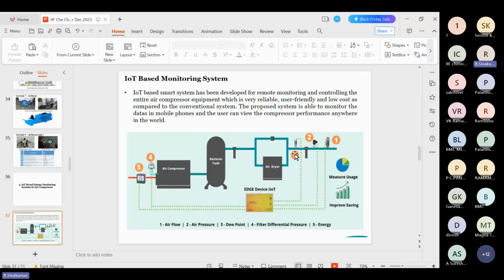There is one device for that. Fourth is the differential pressure, that is the inlet and outlet differential pressure. And finally, the fifth one is the energy meter. If the energy meter is not available, we put our power quality analyzer at the input of the air compressor, so that we monitor the pressure generation and the CFM output, and with respect to the unit consumption, we can arrive at the kilowatt per CFM. The same device can also be used to measure the air leakage quantity.